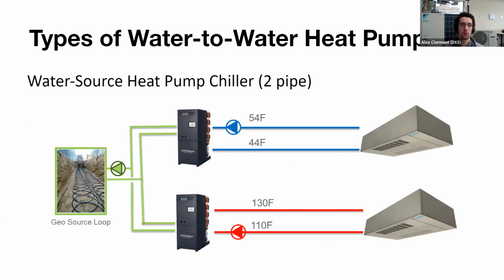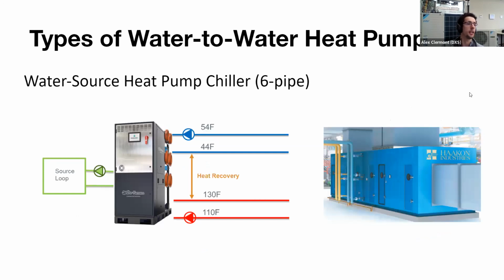Again, this is very similar to air source, but back to the question before, if you do have a geothermal system, you can actually do VRF, as you previously mentioned, but you can also run your hydronic loop through a building, as you can see here. So you go from your geothermal loop and you give hot or cold water to your space. Now on the slide, we see them as 2-pipe machines, so the whole machine has to be in either heating or cooling, but they can also be 6-pipe machines. So they'll actually do heating and cooling using one machine. And this machine would be connected directly to your geothermal loop.